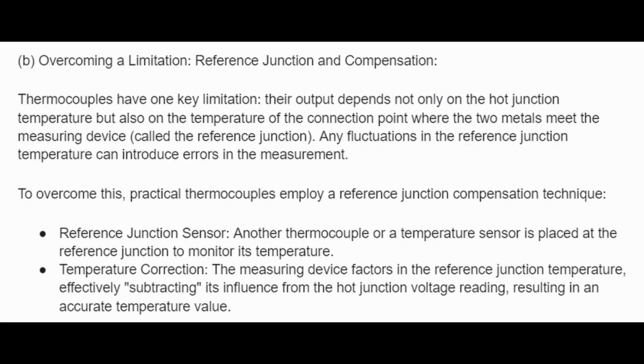Overcoming the limitations. Reference junction and compensation. Thermocouples have one key limitation. Their output depends not only on the hot junction temperature, but also on the temperature of the connection point where the two metals meet the measuring device, called the reference junction. Any fluctuations in the reference junction temperature can introduce errors in the measurement. To overcome this, practical thermocouples employ a reference junction compensation technique.